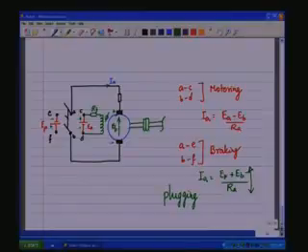The value of IA can be very high, something like 50 to 100 times the rated current. So, the armature windings may or may not be able to handle that. So, it has to be properly designed.